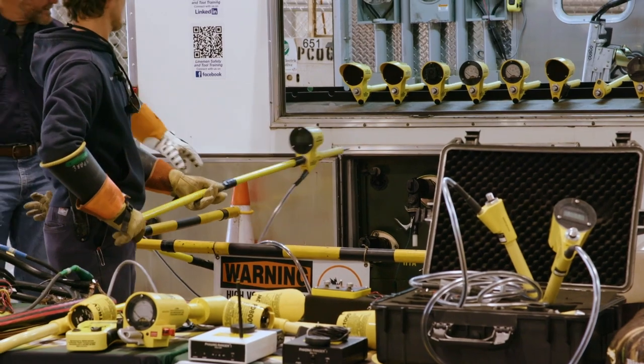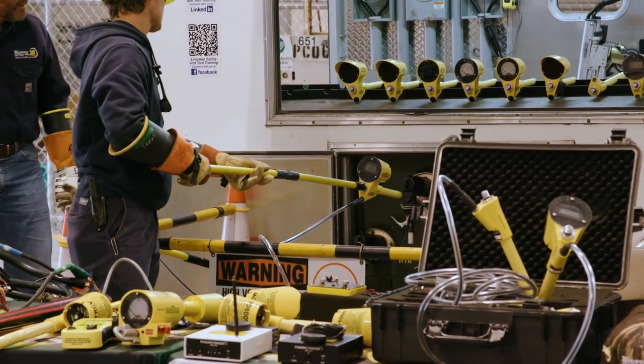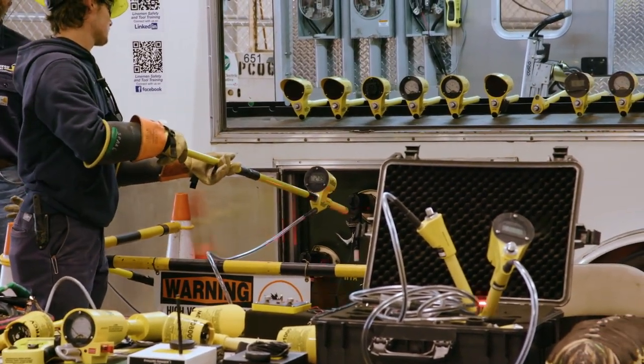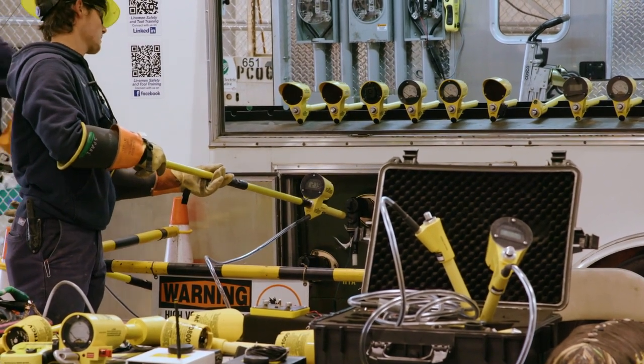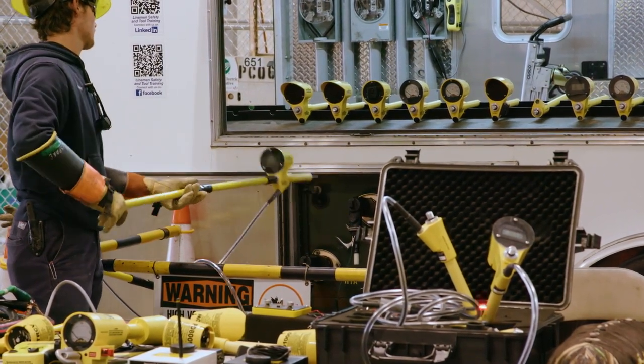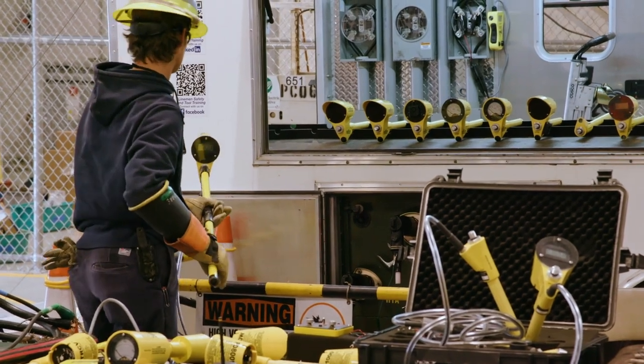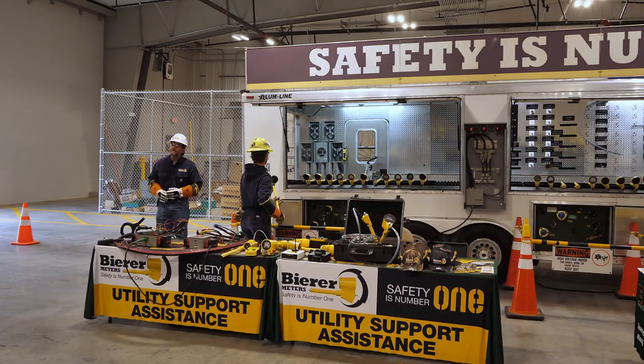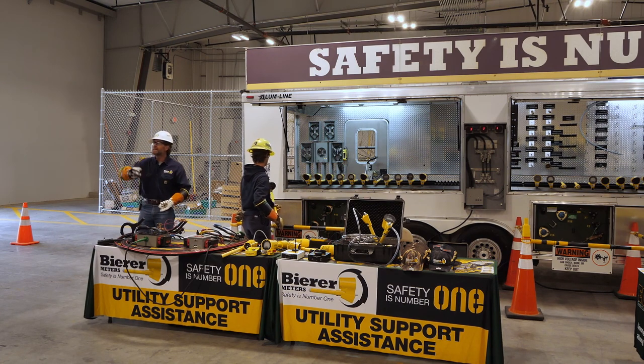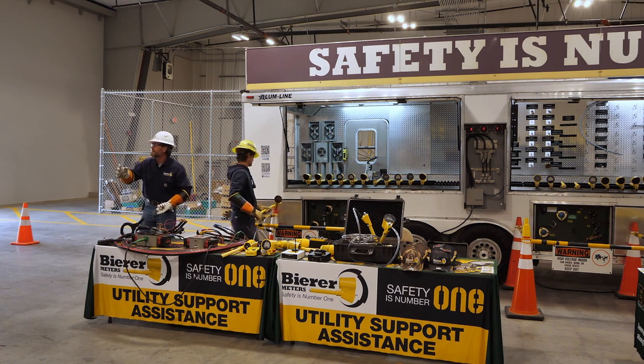Okay, go ahead to the next capacitive test point, the upper one. There you go, what do you get? 279. So we got a difference of about 100 volts, more or less, give or take. So if we're phasing and we're in phase, what we're gonna see is that difference, close to 100 volts. Do the subtraction, get down to close to zero difference, and then you're in phase.